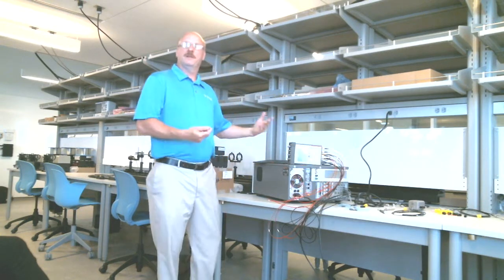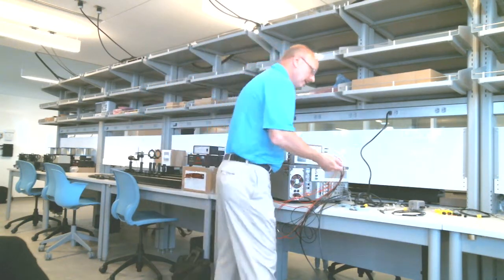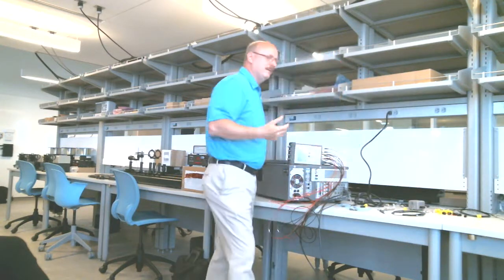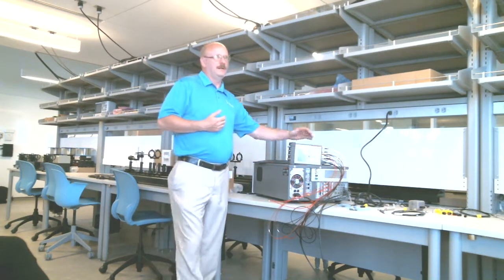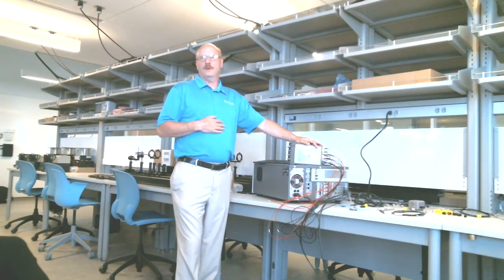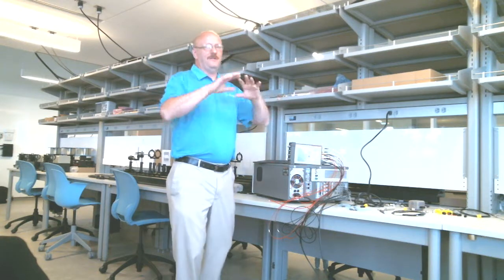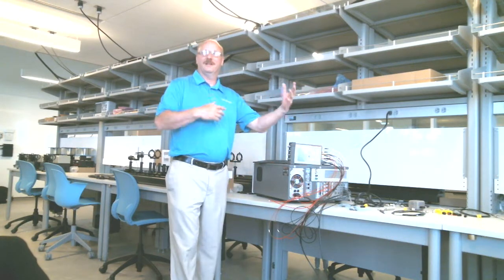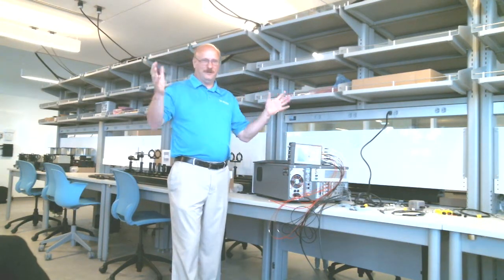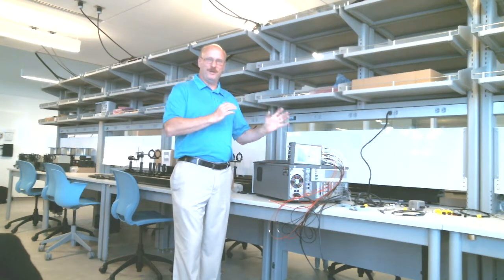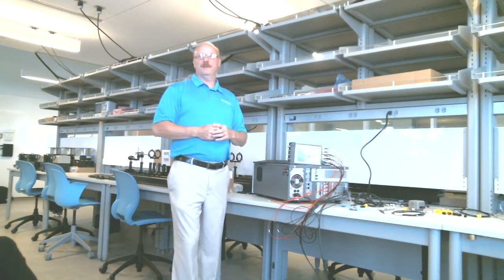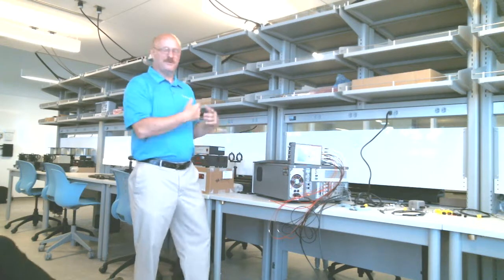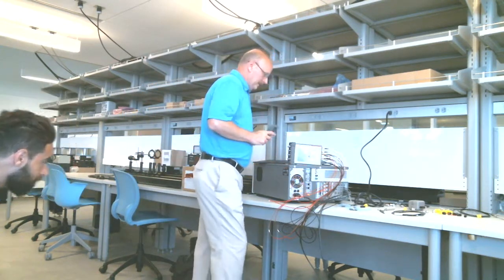You can do a current measurement and it'll tell you what you can get. With these caps on in this environment, you should be able to see noise in the hundreds of femtoamps - that's your noise floor. To get lower than that, you need a Faraday cage, with shielding and guarding. All the stars have to align - when you want to get below that, you've got to be in the right environment. The system's capable, but you need the right equipment to do it.